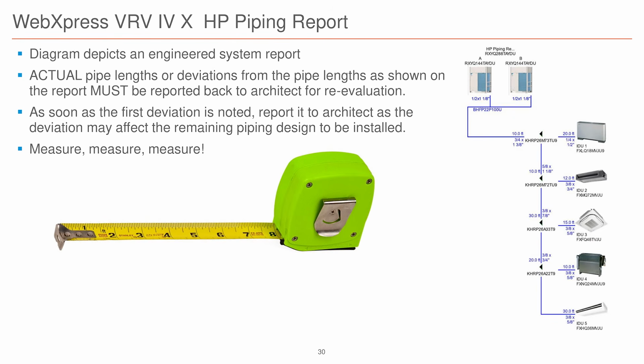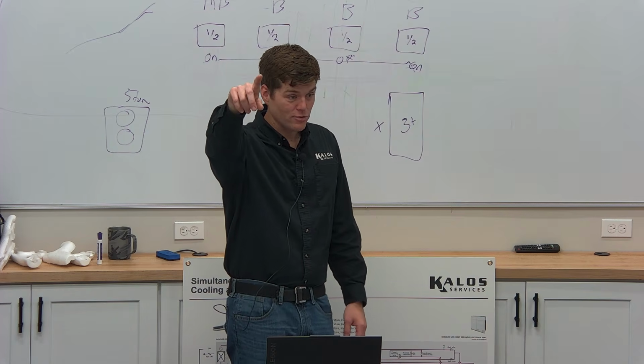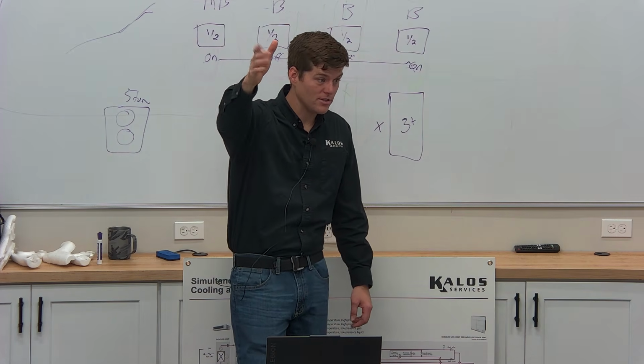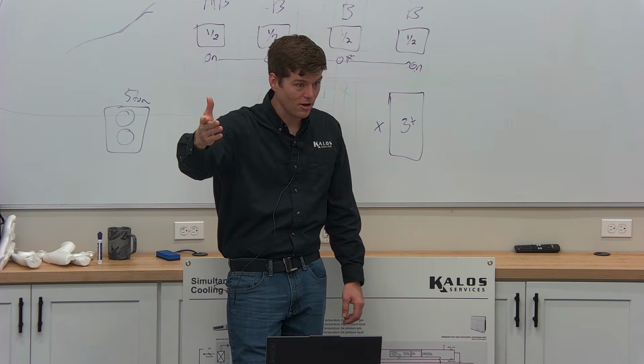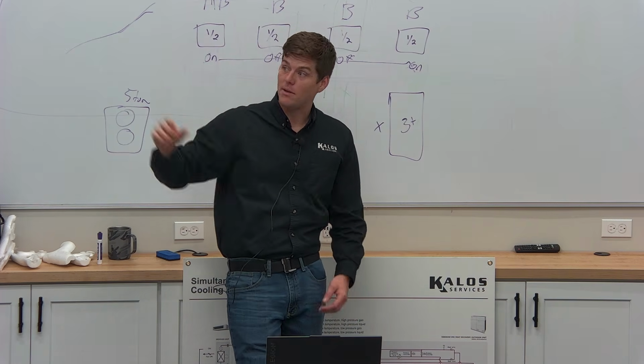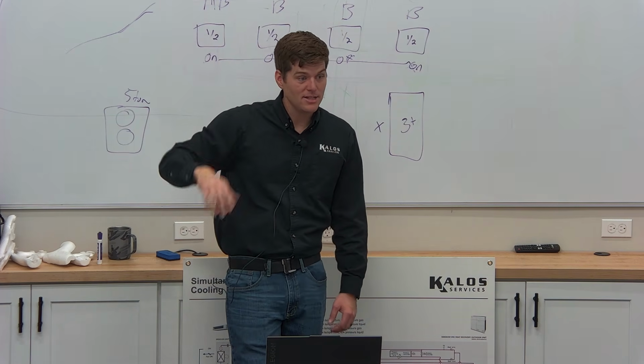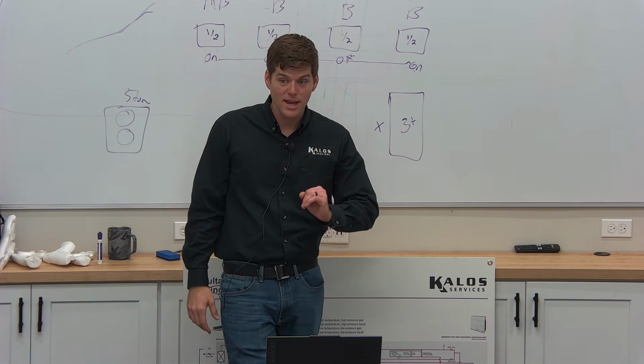So the reason the measurement of the lines are so important is, one, it's refrigerant charge, but two, your distances determine the diameter of the pipe. If I've got a 3-ton unit that's 25 feet away and I've got a 3-ton unit that's 350 feet away, I have to account for those restrictions. That's a long way to go. It's additional friction in the pipe itself. And so my computer program tells me to take that liquid line from 3/8 and make it 1/2 inch.